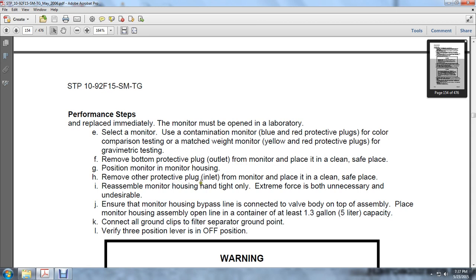Reassemble the monitoring housing, hand tighten only. Extreme force is both unnecessary and undesirable. Ensure that the monitoring housing bypass line is correctly connected to the valve on the top of the assembly. Place the monitoring housing assembly on the open line in a container of at least 1.3 gallons or 5 liters capacity. Connect all ground clips to the filter separator ground point.